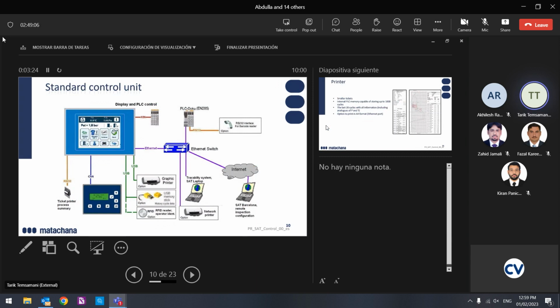The blue one is the switch, the machine switch. So we have the screen. The screen has an X2X connection with the PLC directly, and we have a cable, the purple line, the Ethernet cable to the switch. The switch also has an Ethernet cable to the PLC. So we only find in the machine two Ethernet cables, one from the switch to the screen and the other from the switch to the PLC. Sometimes, if we don't have communication between PLC and screen, we can put this cable directly from the PLC to the screen. If we suspect that the problem comes from the switch, we can connect directly from the PLC to the screen to check if there is also a problem.